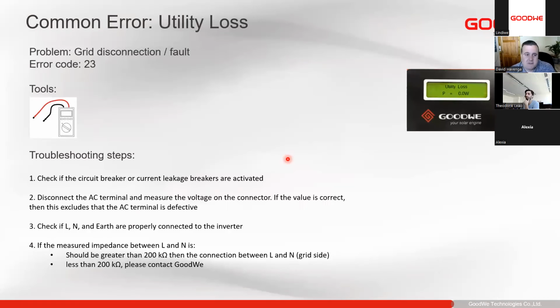Next is utility loss. So utility loss is obviously the inverter is not seeing any utility power on the inverter itself. So we can check if the circuit breaker or current leakage device is on. We can disconnect the AC terminal and measure the voltage on the connector to see whether the voltage is correct under the connector.